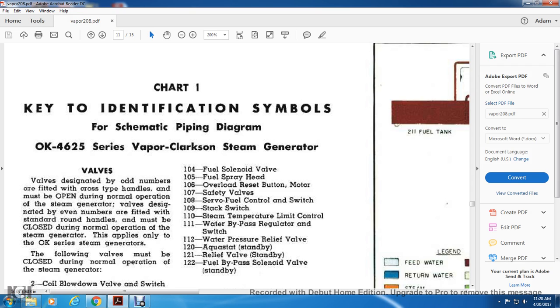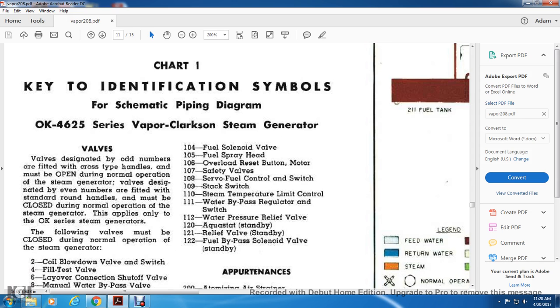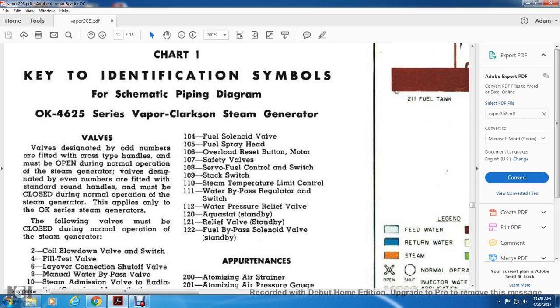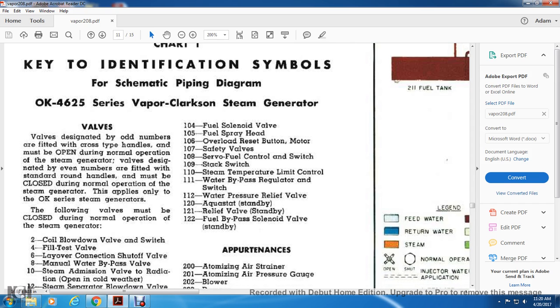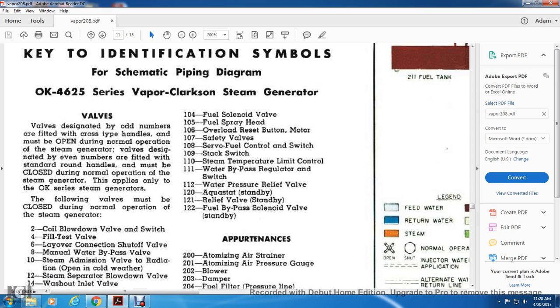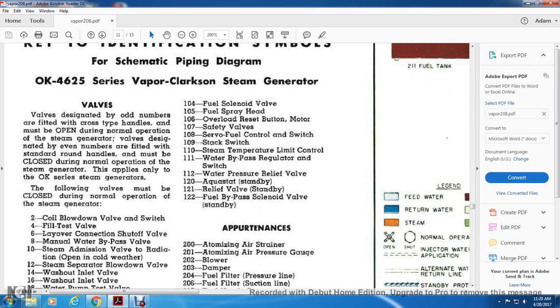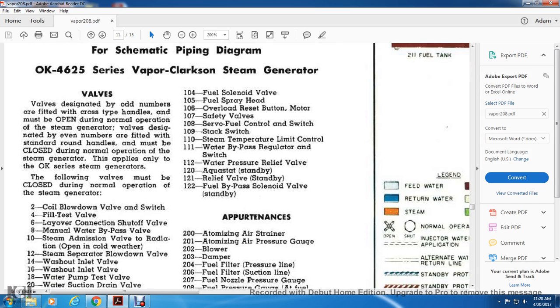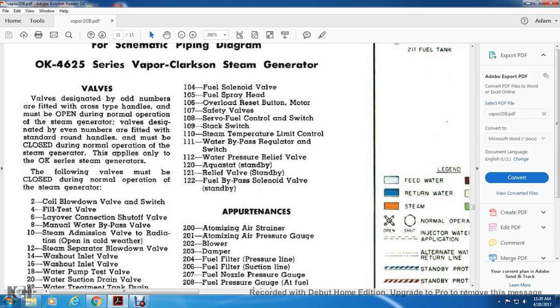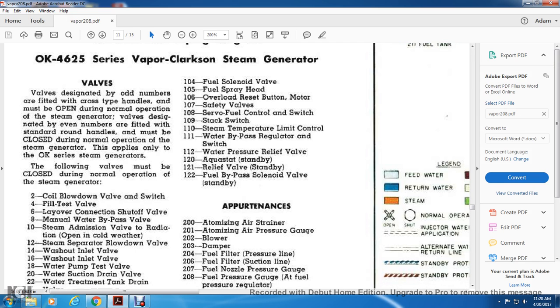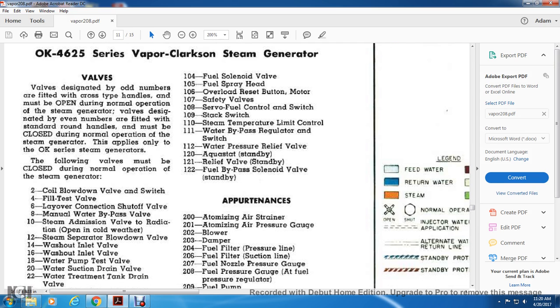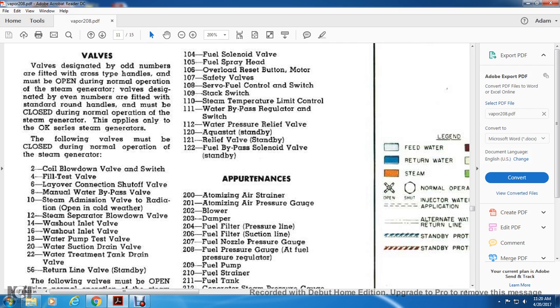The following valves must be closed during the normal operation of the steam generator: coil blowdown valve, switch, Fill-Test Valve, layover connection shutoff valve. 8, manual water bypass valve. 10, steam admission valve with the radiation open in cold weather. 12, steam separator blowdown valve. 14, washout inlet valve. 16, washout inlet valve. 18, water pump test valve. 20, water suction pump drain valve. 22, water pump treatment tank drain valve. 56, return line valve standby.